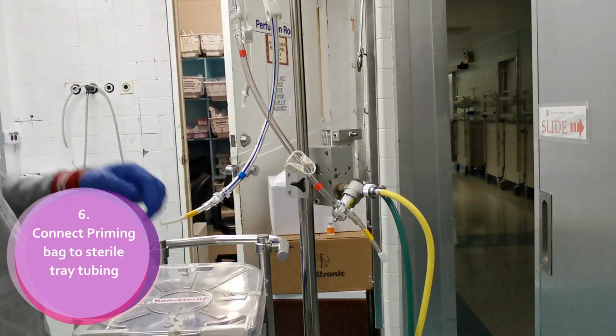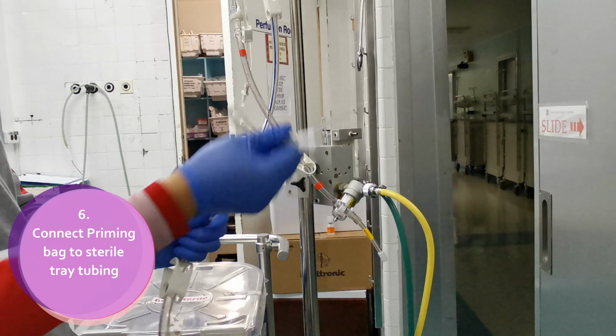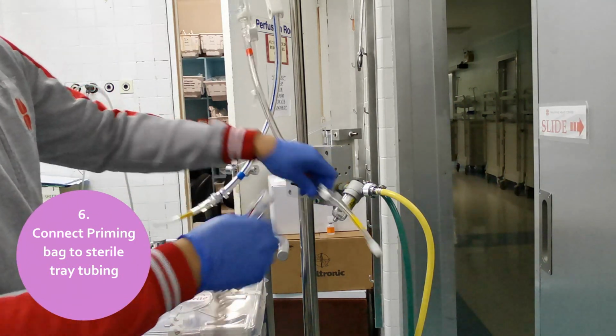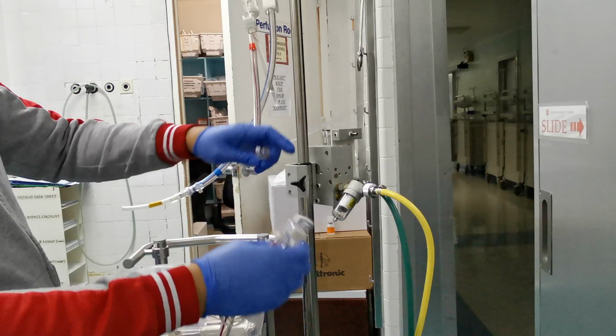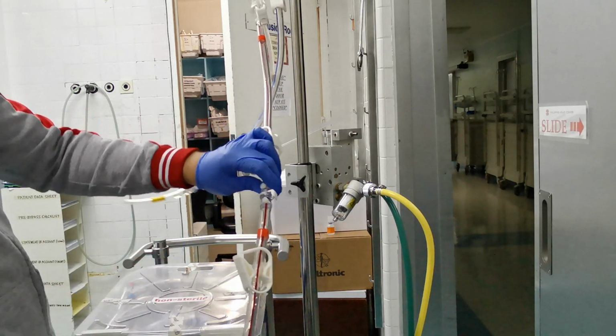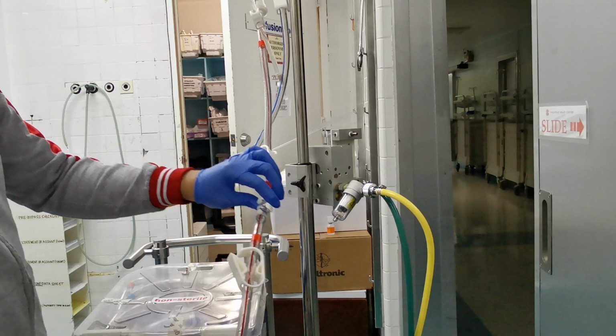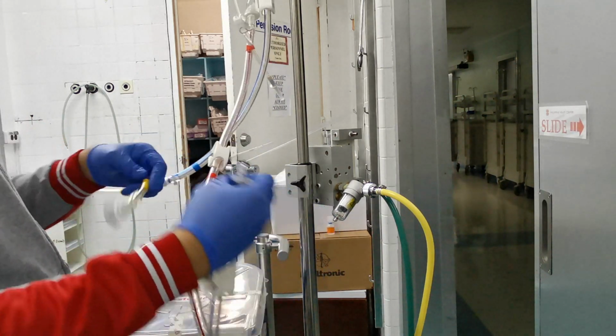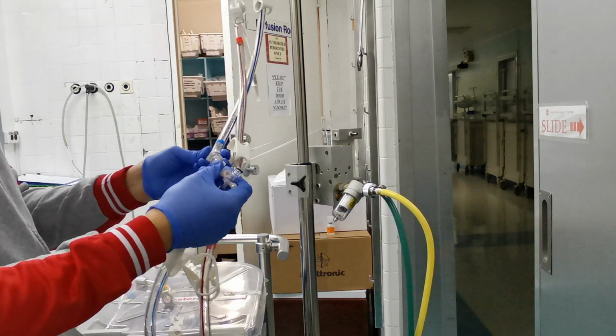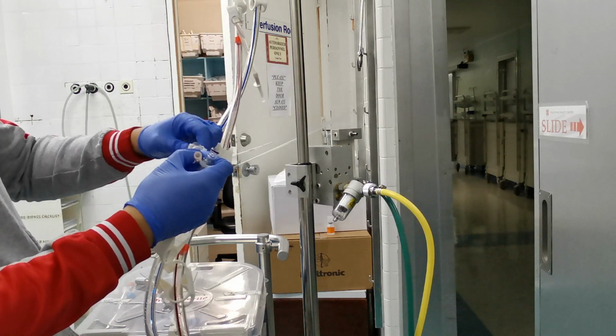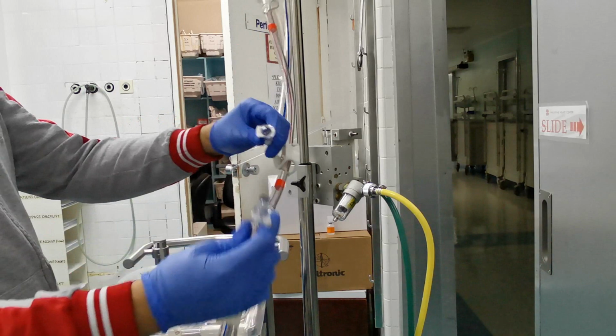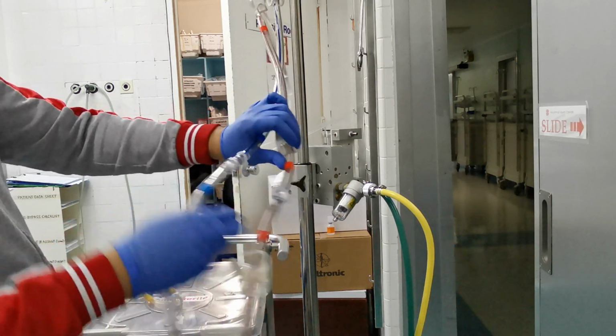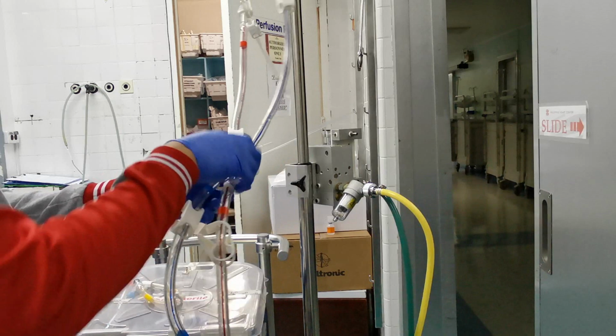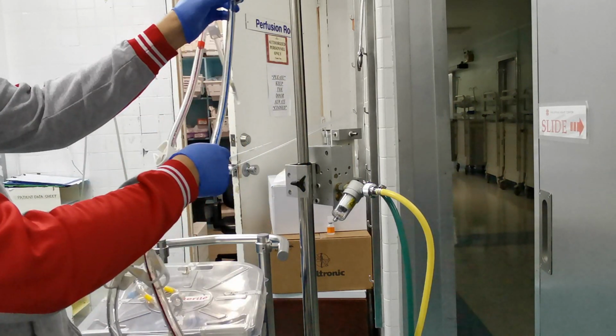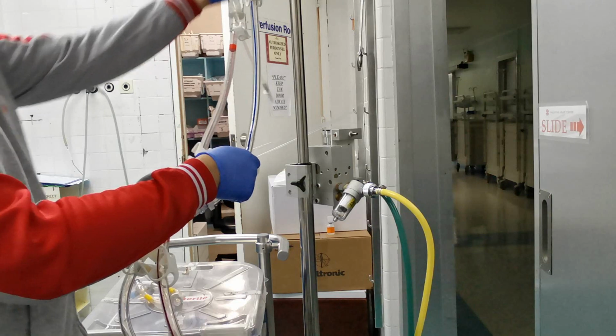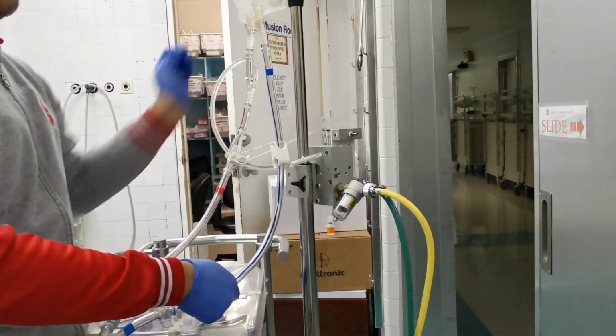Disconnect the distal end tubings on the sterile tray and the distal end tubings of the priming bag. Make sure that the blue line is clamped. Connect the distal ends of both tubings from the sterile tray and priming bag. Make sure that the blue and red lines are connected to the same appropriate color. This is to avoid confusion between the arterial and venous line. Again, make sure that the blue line is clamped.